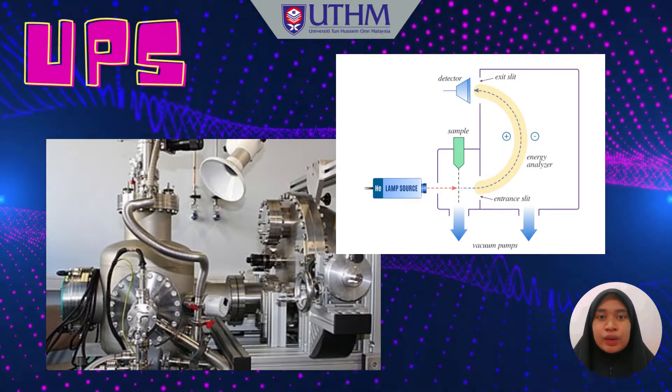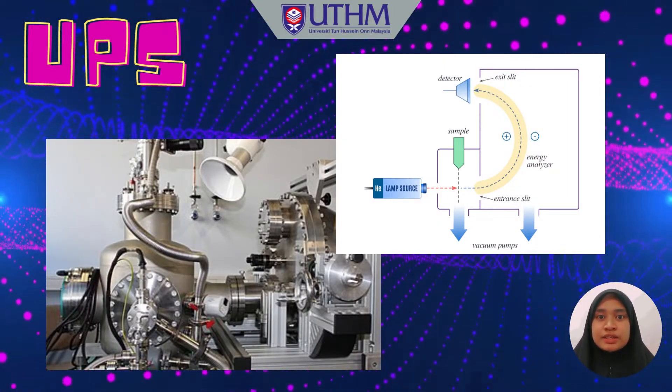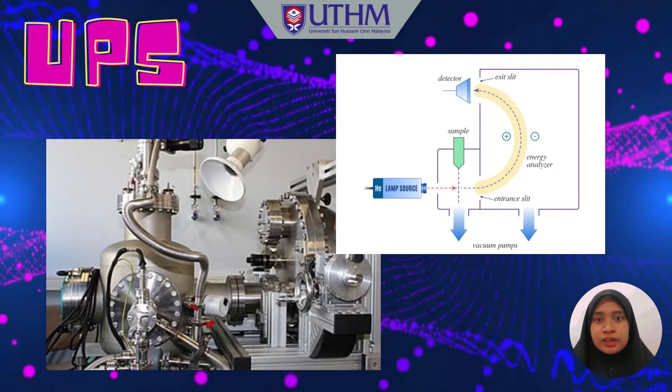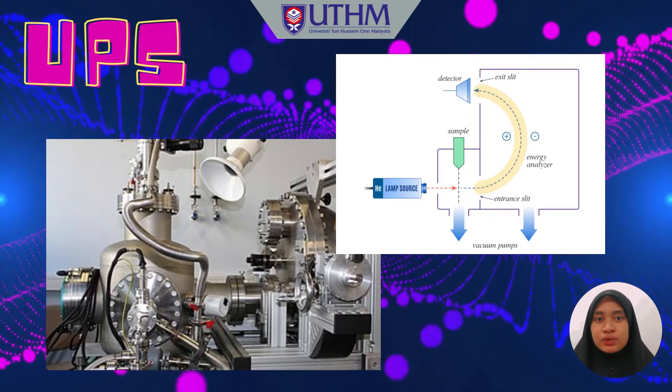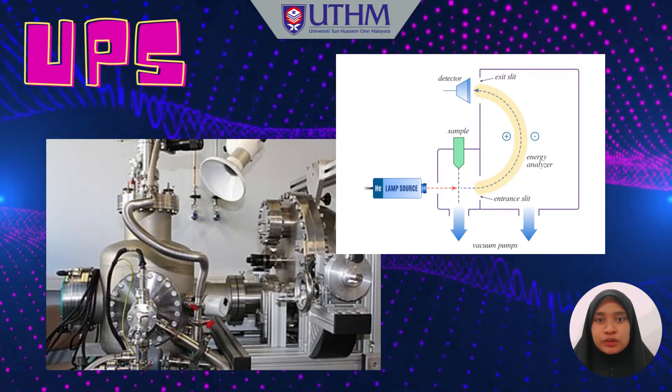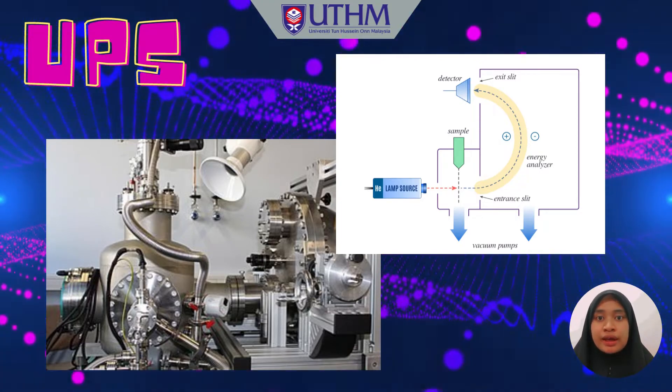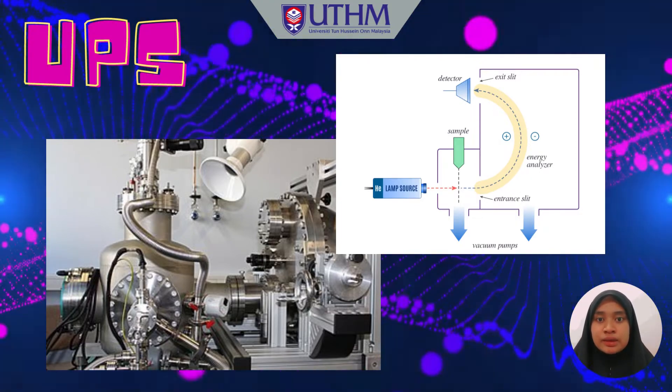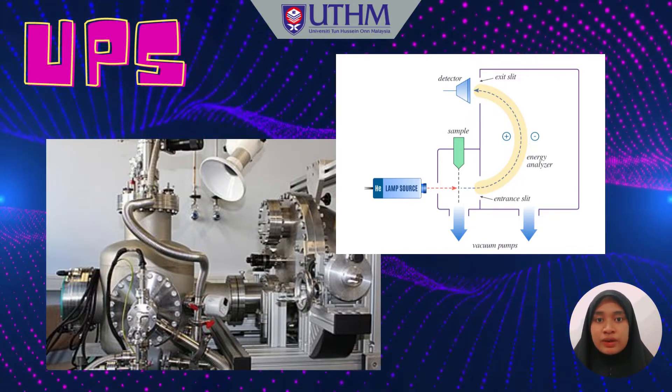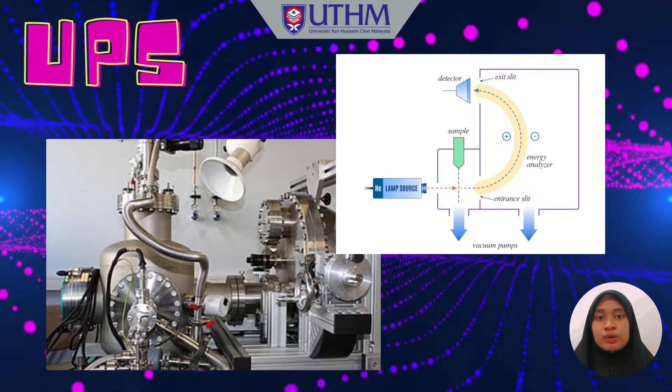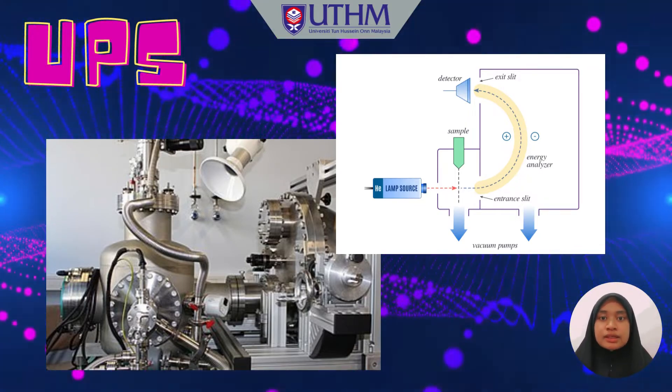This is the diagram of a basic typical PES instrument used in UPS where the radiation source is a UV light source. When the sample is irradiated, the released photoelectrons pass through the lens system which slows them down before they enter the energy analyzer. The analyzer shown is a spherical deflection analyzer which the photoelectrons pass through before they are collected at the collector's slit.